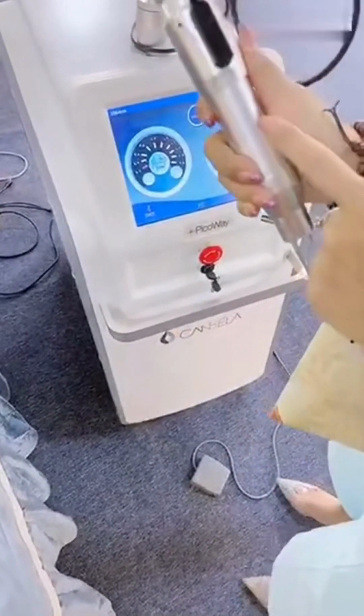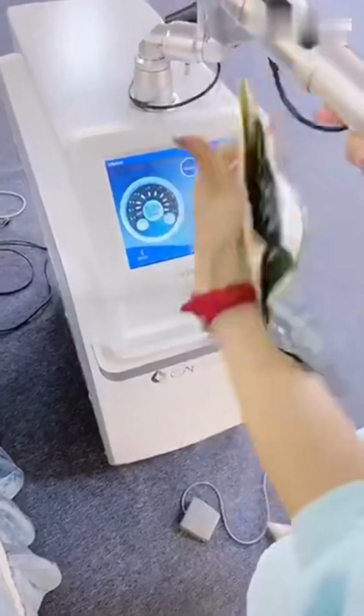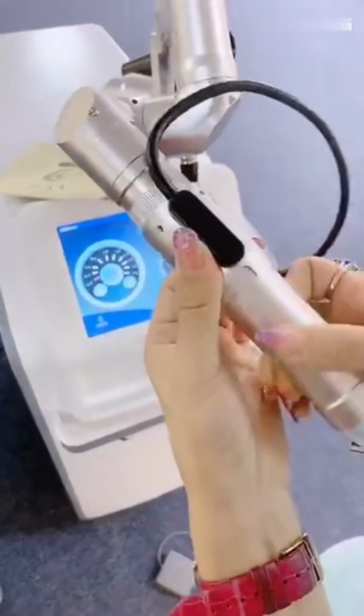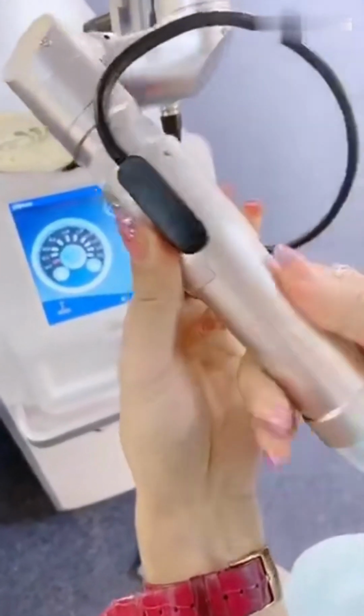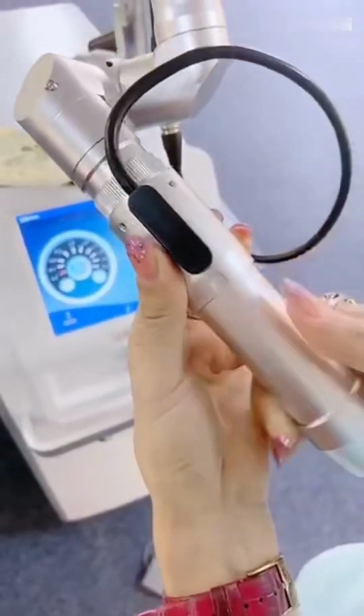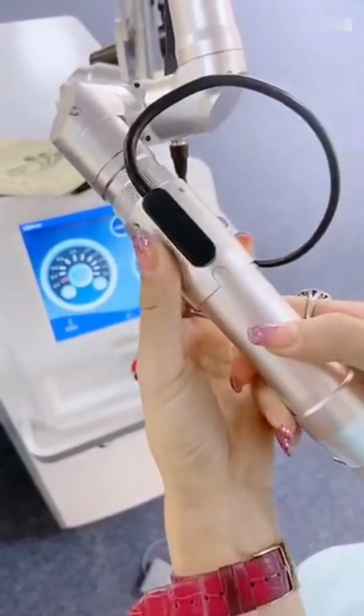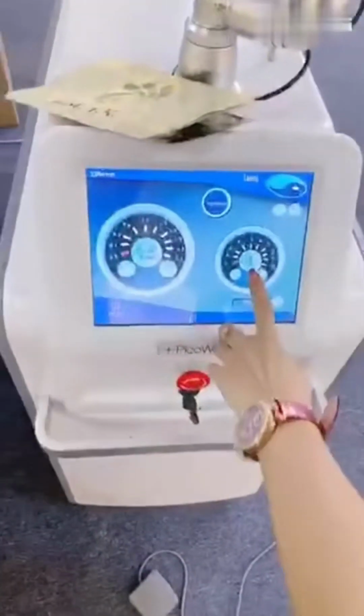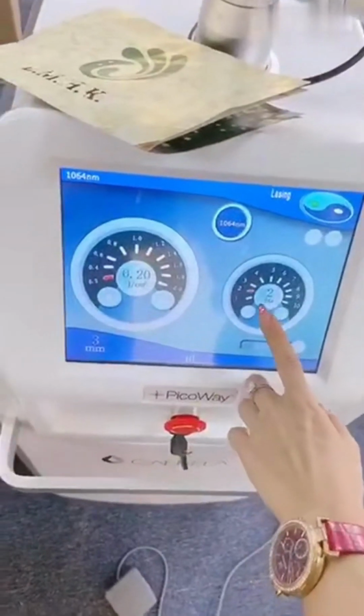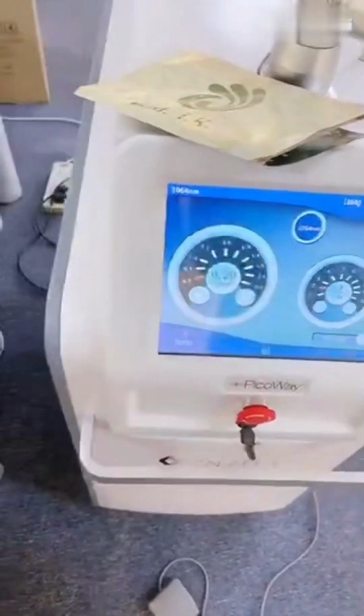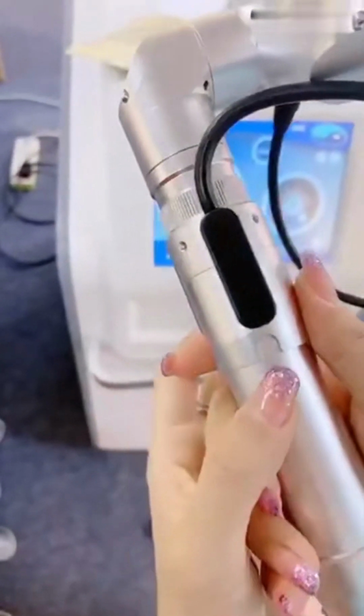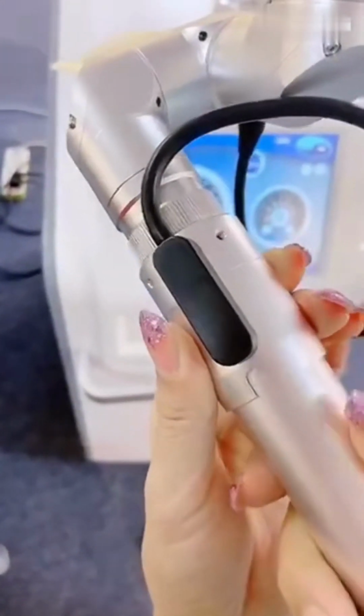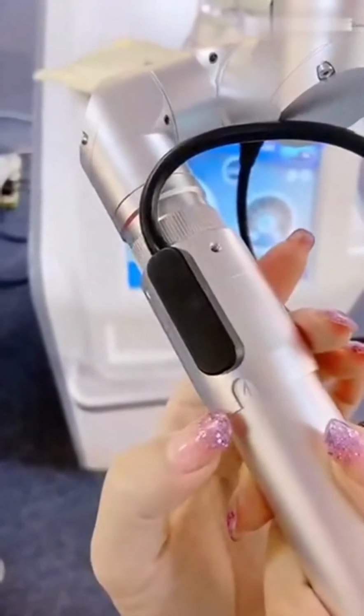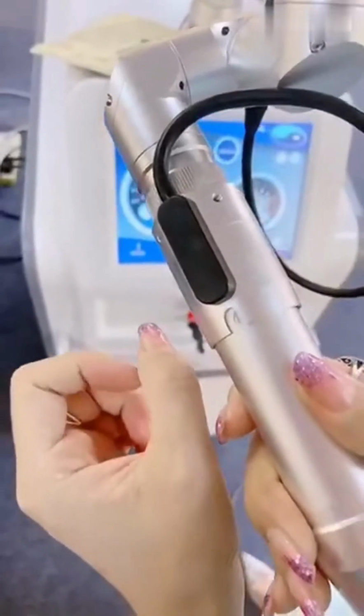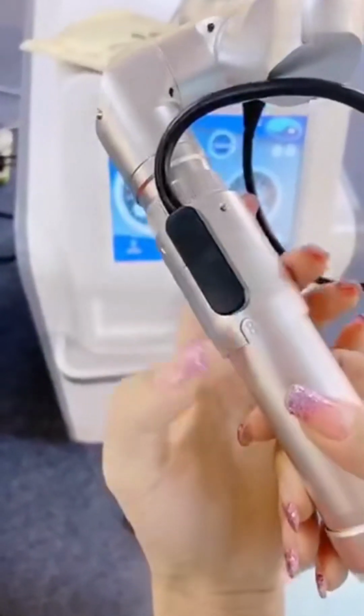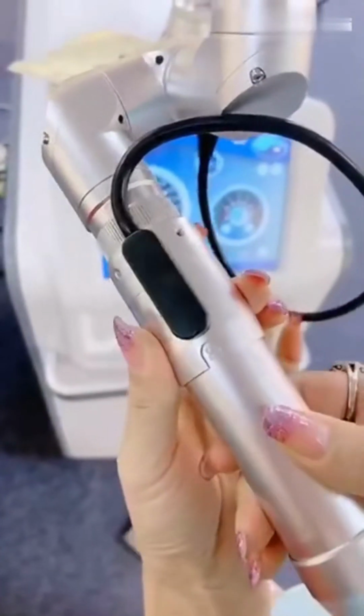Now I'll explain the practical operation during treatment. Here you can adjust the spot size from 2x2 to 10x10. Rotate this laser probe to adjust the spot size. We also need to change the frequency. The frequency needs to be set to 2 or 3 Hz. For aesthetic treatments, we typically set the spot size to 3, or can adjust it to 4. The larger this number, the larger the laser spot size becomes. A larger spot size disperses the laser energy more widely. For treating large areas of melasma, you can set it to 8 or 7.